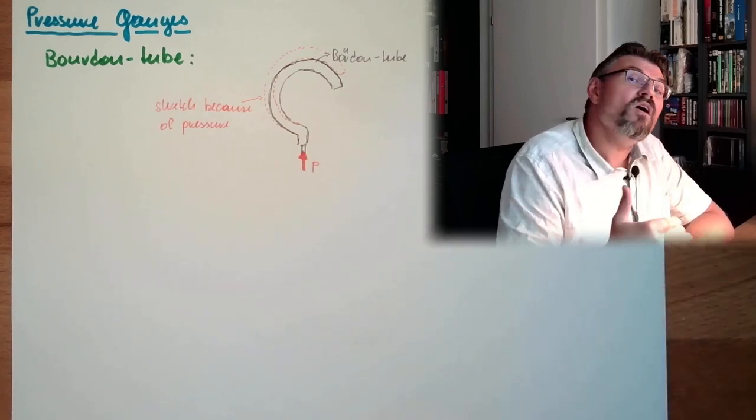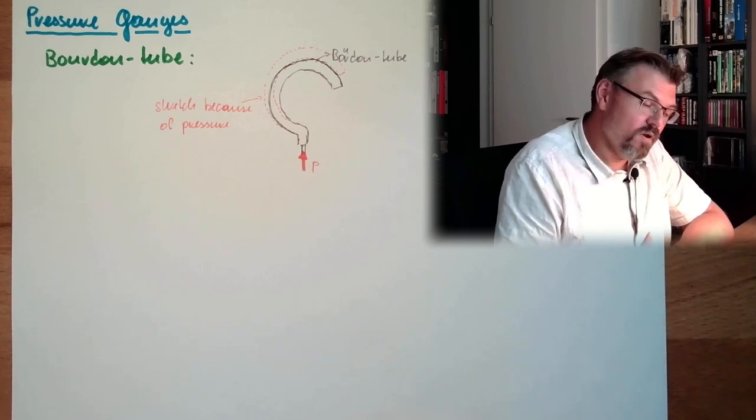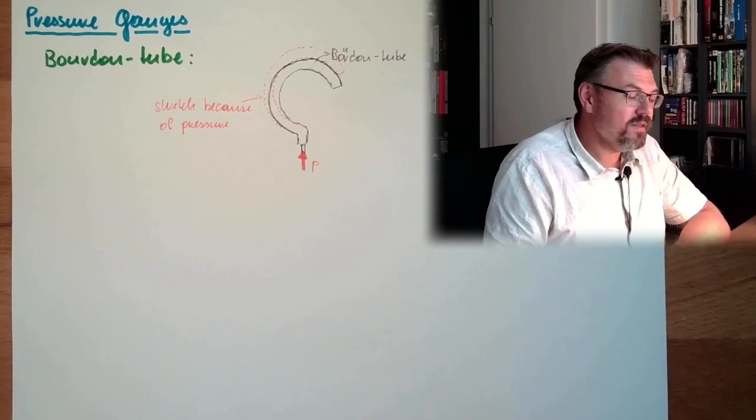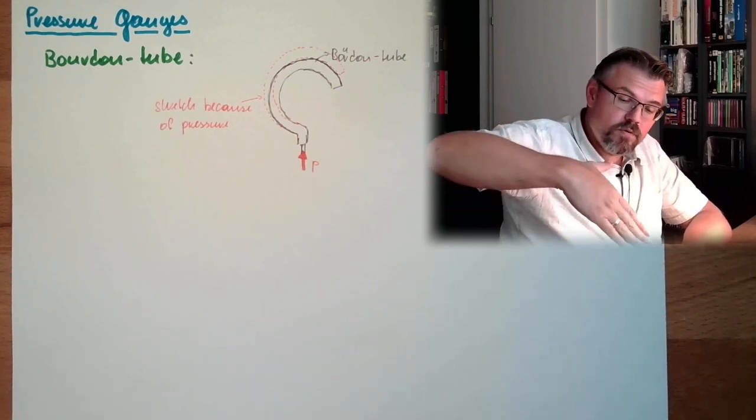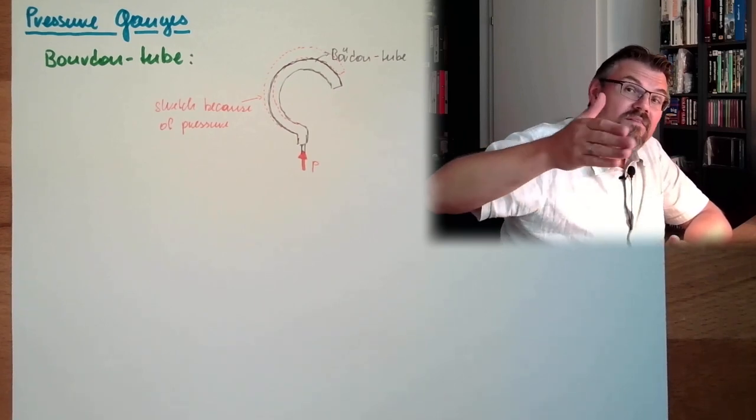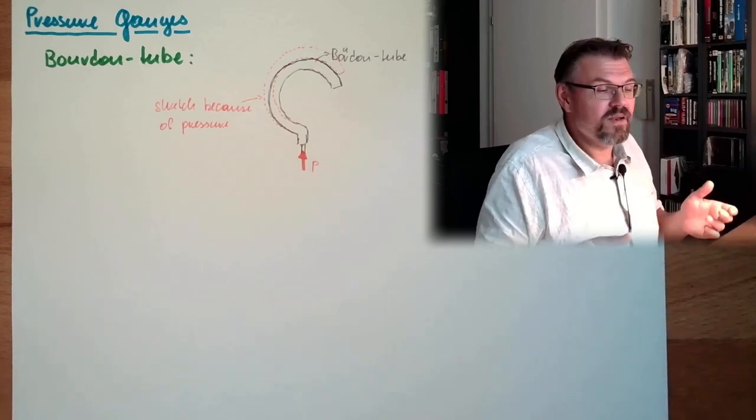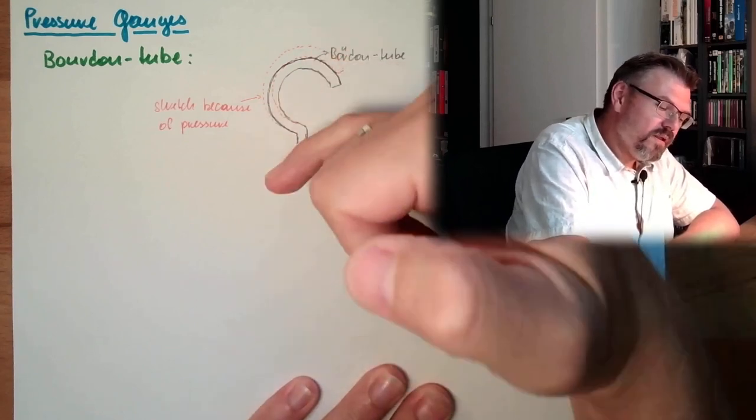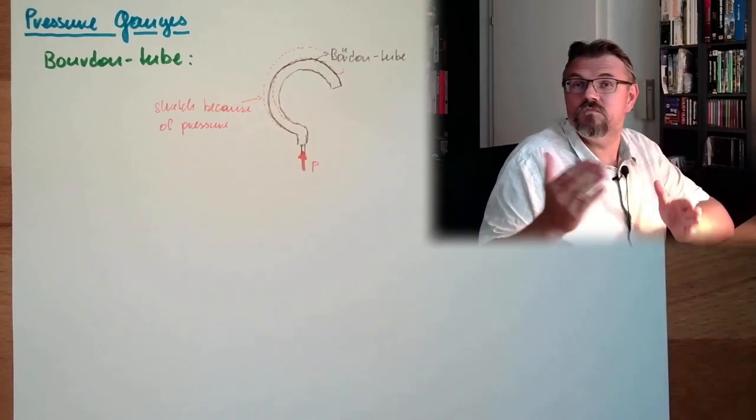Sensitivity is good. However, it's sensitive to overload. And if you ever have a pressure gauge where the pressure is already indicated when it's not loaded at all, then you know it was overloaded once and it will stay deformed and already shows something.